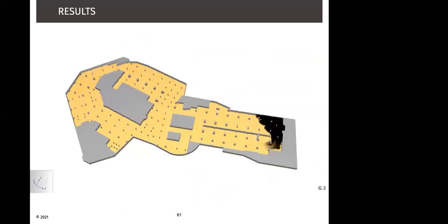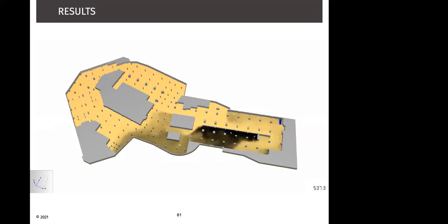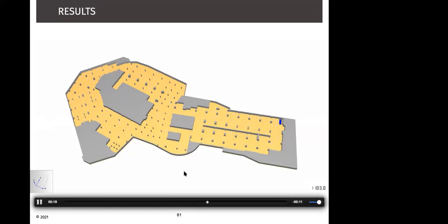And how that helps is, with the same fire location, you're able to move the smoke into the exhaust shafts rather than being blocked by that wall of air. And you have the smoke cleared out by 900 seconds. I'll say that again.